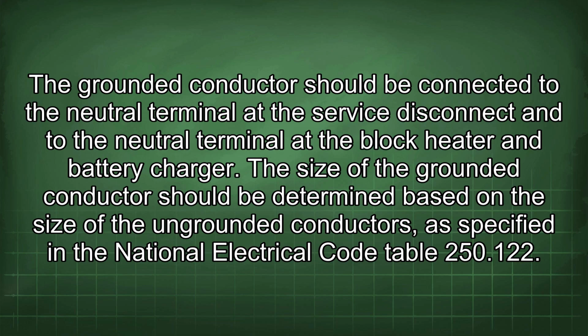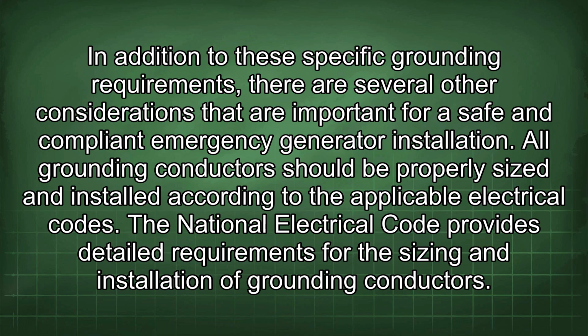The size of the grounded conductor should be determined based on the size of the ungrounded conductors, as specified in the National Electrical Code Table 250.122. In addition to these specific grounding requirements, there are several other considerations that are important for a safe and compliant emergency generator installation. All grounding conductors should be properly sized and installed according to the applicable electrical codes. The National Electrical Code provides detailed requirements for the sizing and installation of grounding conductors.